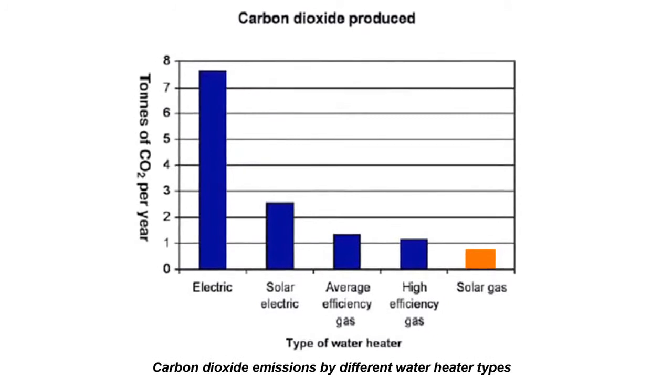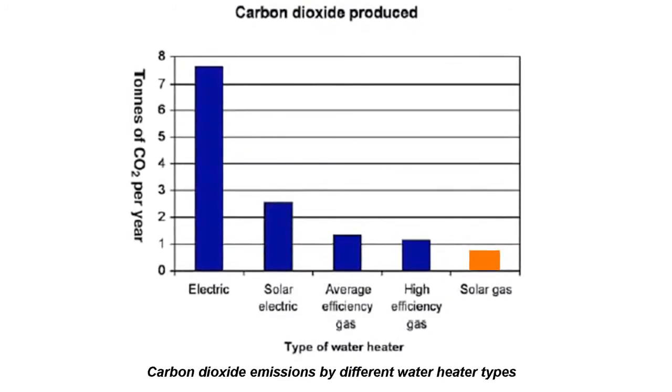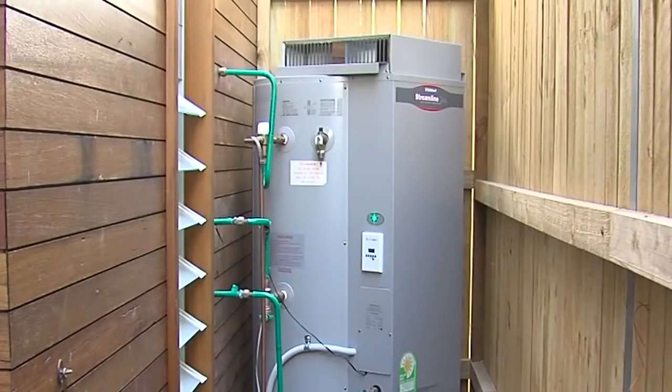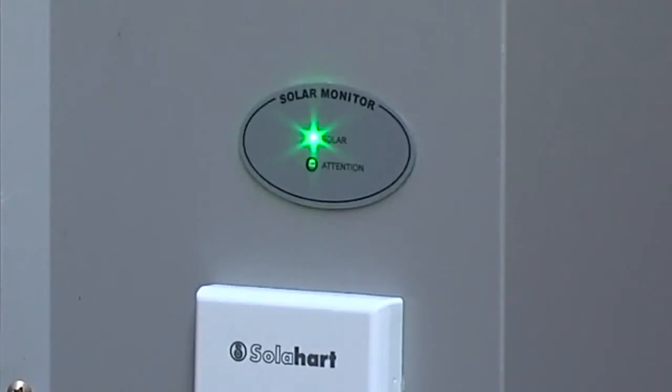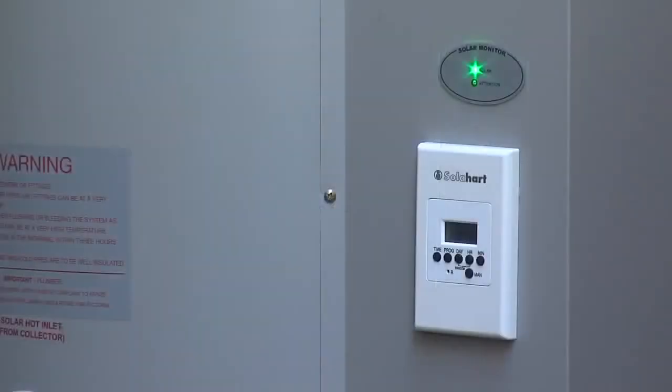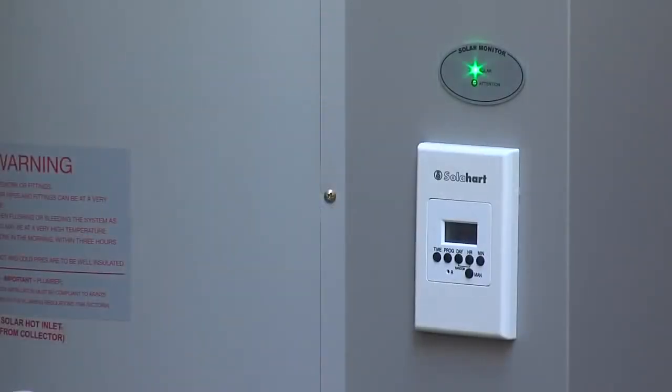Natural gas boosters have the advantage of lower emissions and running costs compared to electric boosters and also aren't subject to time of use restrictions. Install a timer on gas storage boosters to ensure the gas does not heat water which would otherwise be heated by the sun.